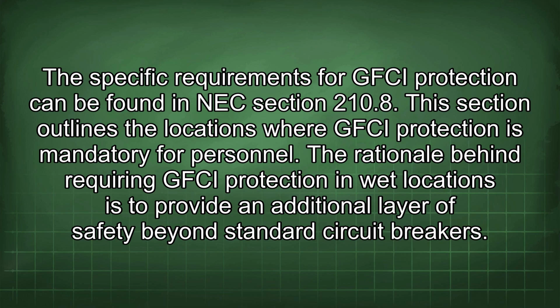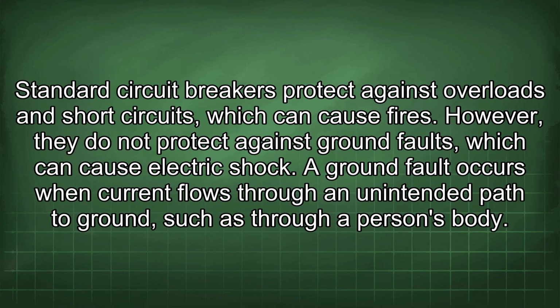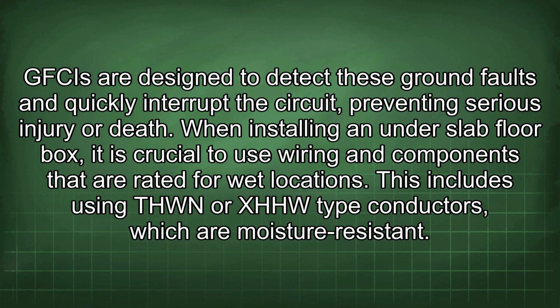The rationale behind requiring GFCI protection in wet locations is to provide an additional layer of safety beyond standard circuit breakers. Standard circuit breakers protect against overloads and short circuits, which can cause fires. However, they do not protect against ground faults, which can cause electric shock. A ground fault occurs when current flows through an unintended path to ground, such as through a person's body. GFCIs are designed to detect these ground faults and quickly interrupt the circuit, preventing serious injury or death.